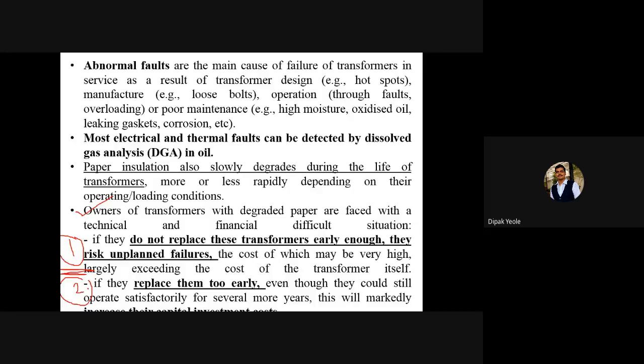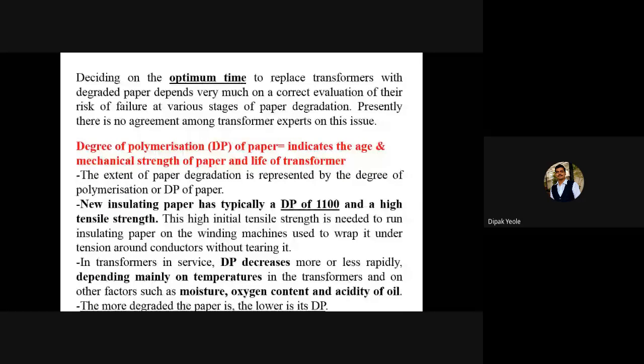There is a technique available called degree of polymerization. Degree of polymerization indicates the age, or you can say life, and mechanical strength of the paper and the total transformer life. Generally the company mentions a value of about 1100, which indicates the DP value has a high tensile strength. So generally the new insulating paper shows the 1100 value and has high tensile strength.